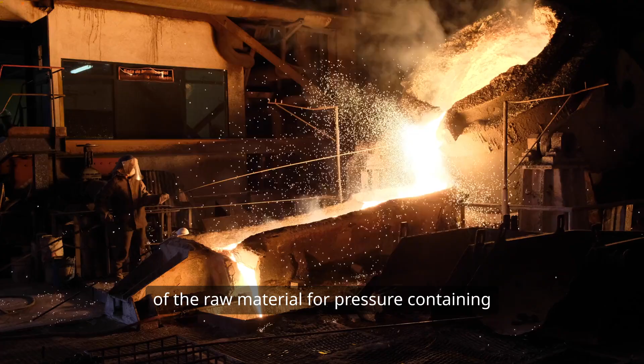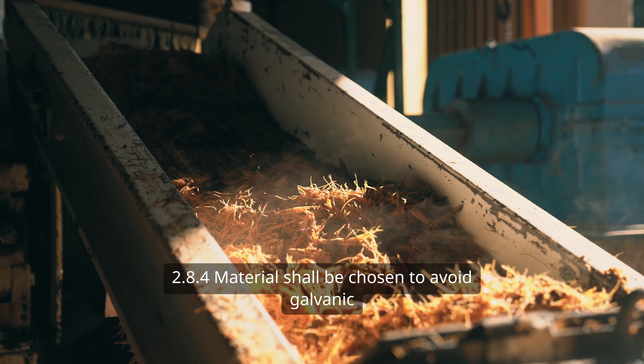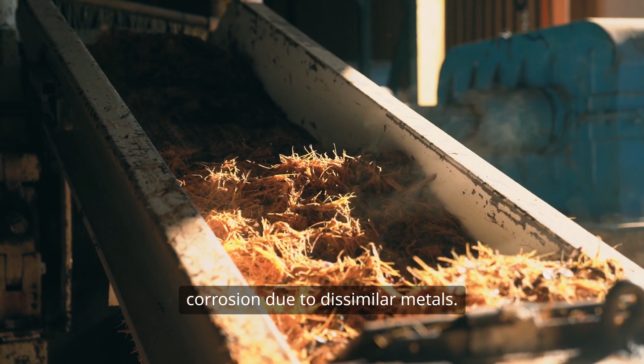2.8.3. The vendor shall furnish material certificates giving chemical composition, mechanical data, and the country of origin of the raw material for pressure-containing parts and for all main components of the heater. 2.8.4. Material shall be chosen to avoid galvanic corrosion due to dissimilar metals. 2.8.5. All material shall be new and be identifiable against their certification.